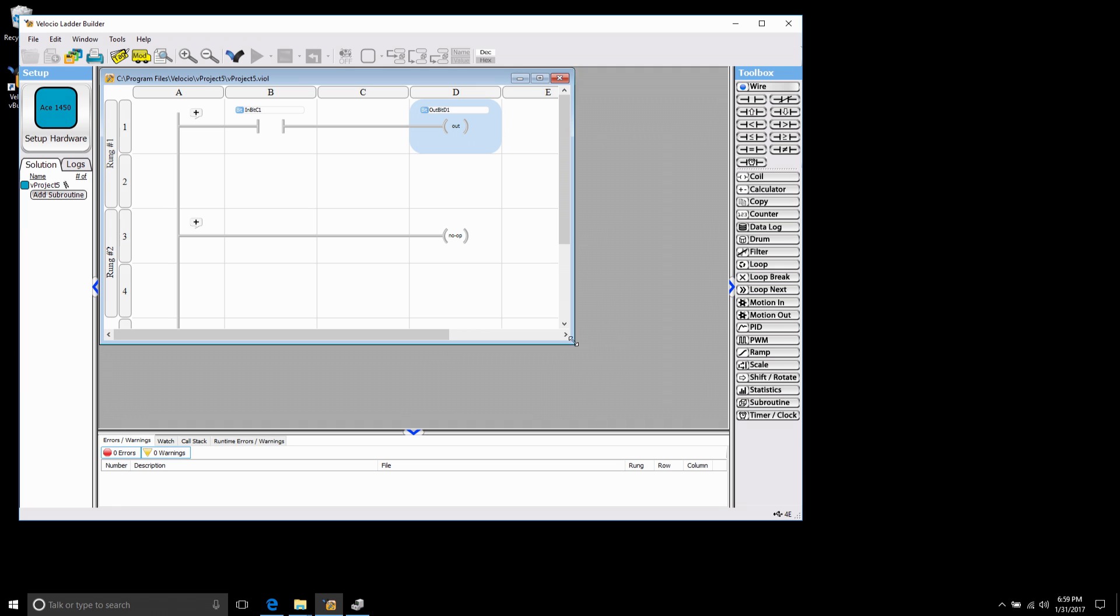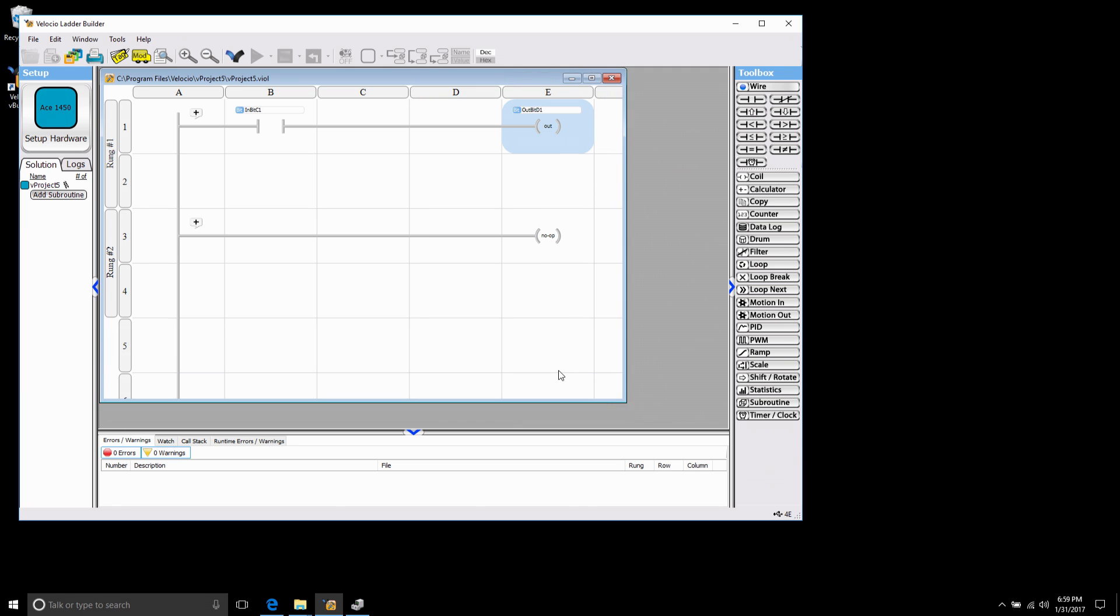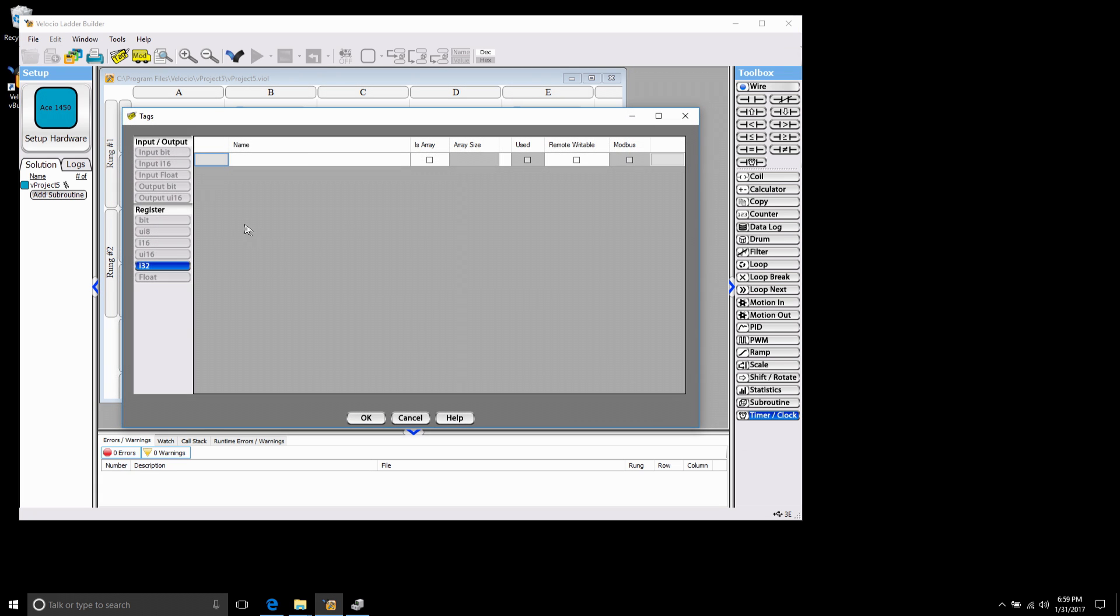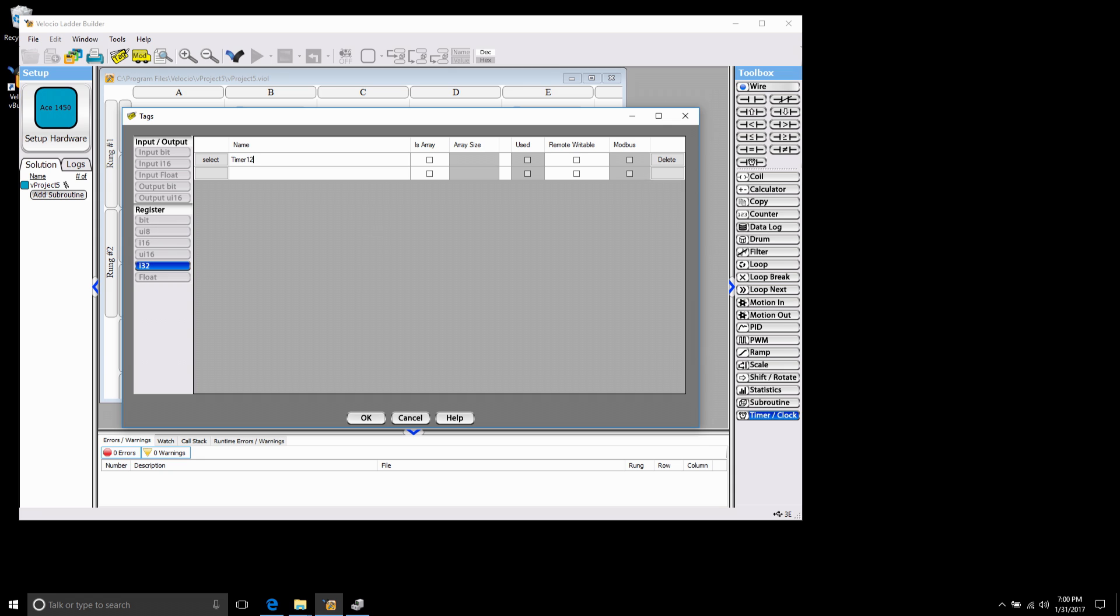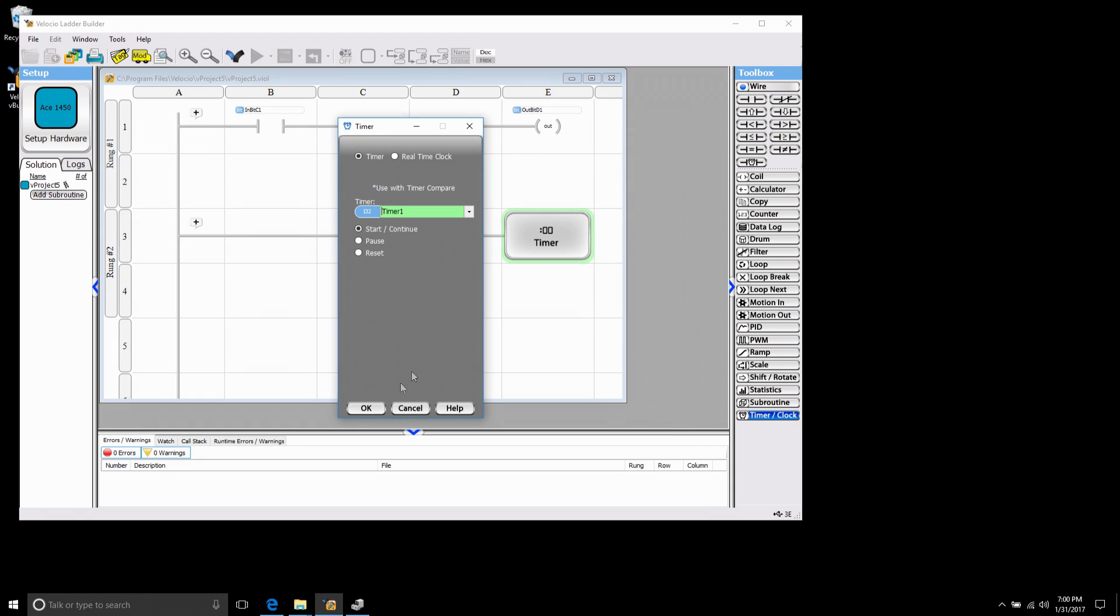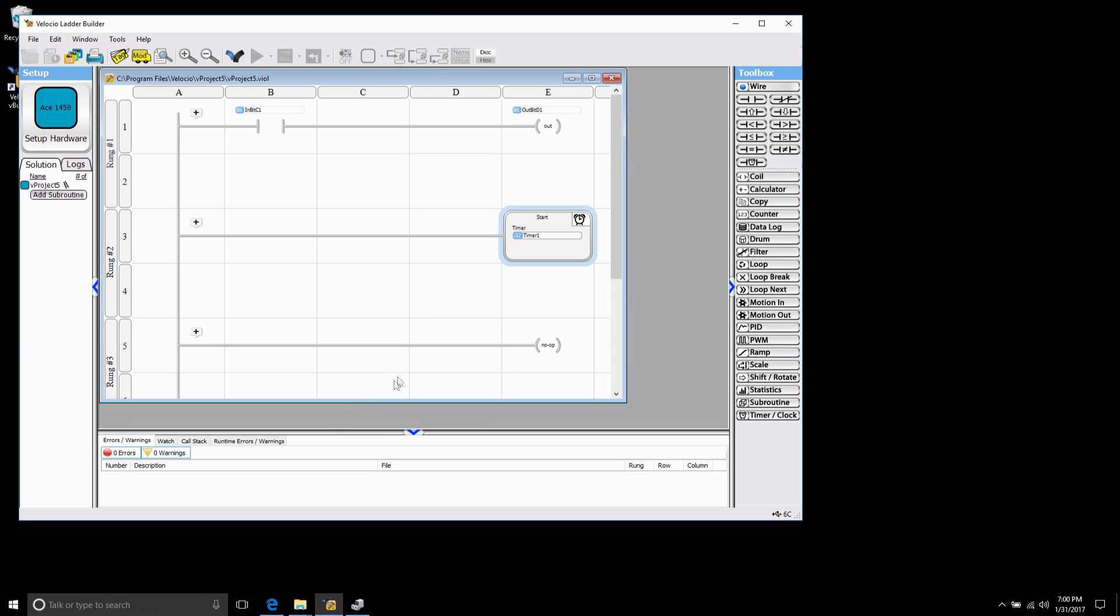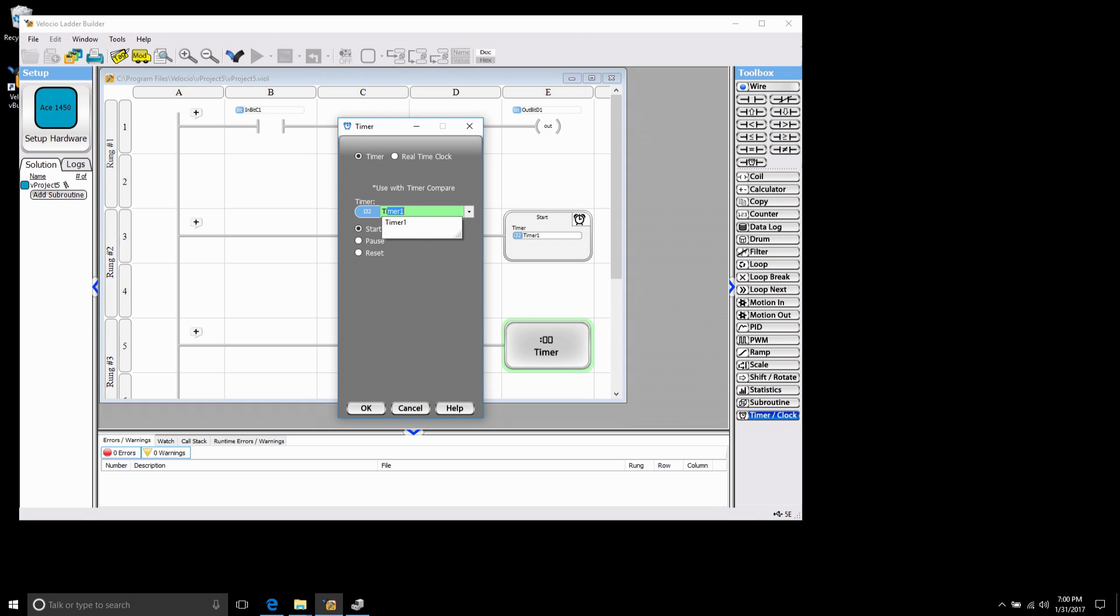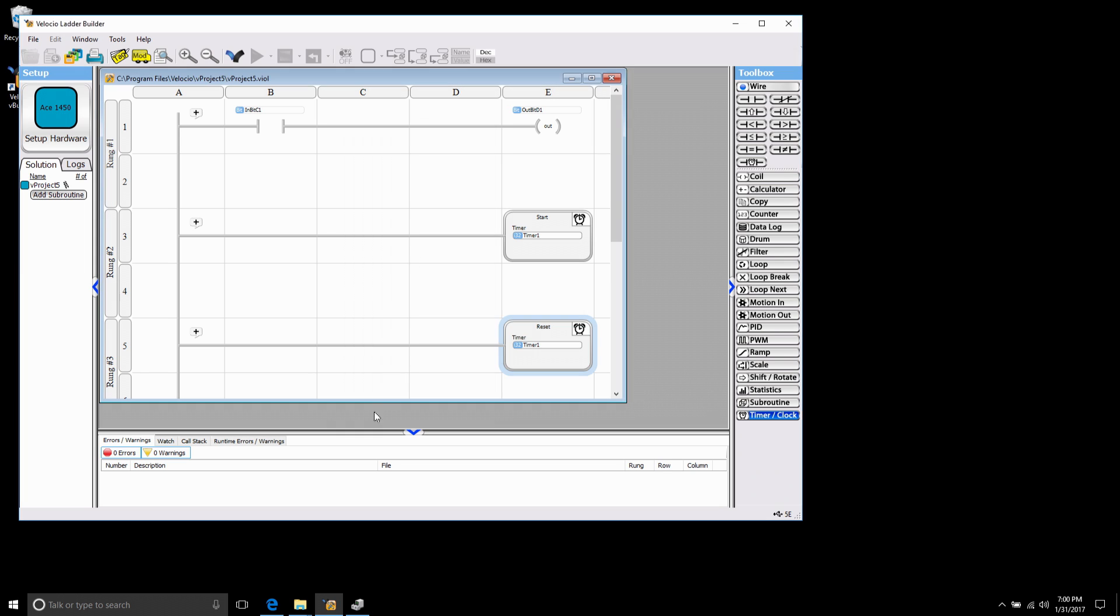Now the next thing I want to do is make a free running timer. I'm going to come down here to timer clock, drop this in. Now go to my tag editor. I see by default it puts me as integer 32. So what I'm going to do is create a 32-bit integer and I'm going to put in the name timer1. Now what I want to do is after three seconds I want this timer to reset and start again. So I'm going to add another timer clock and this time I'm just going to type in my timer1 tag. Now this block I want it to reset.